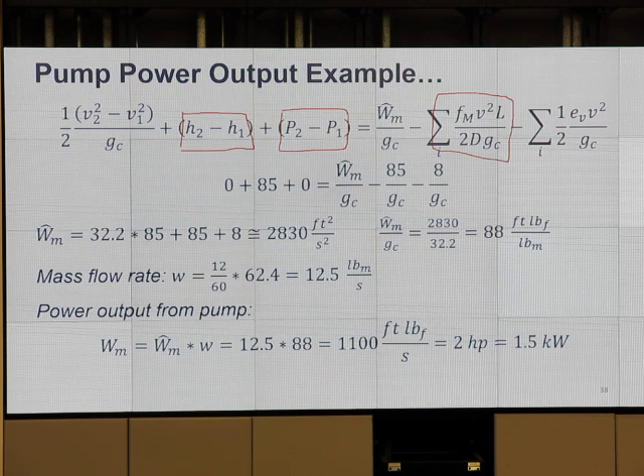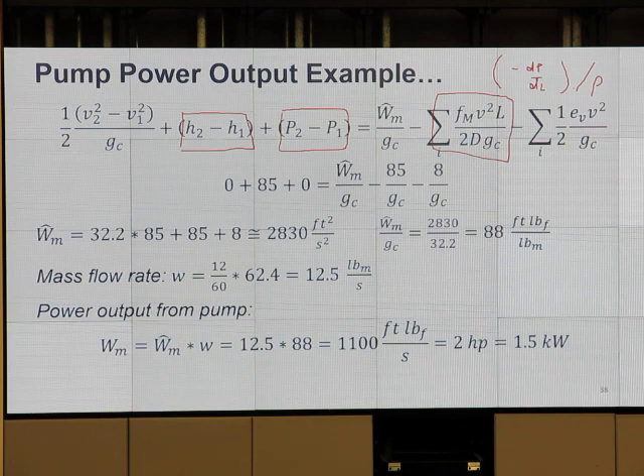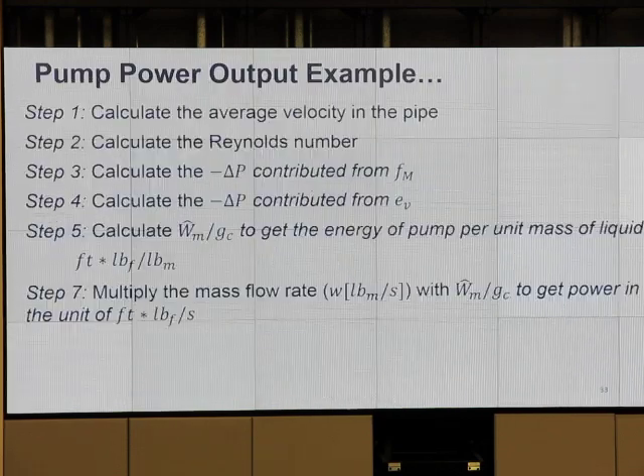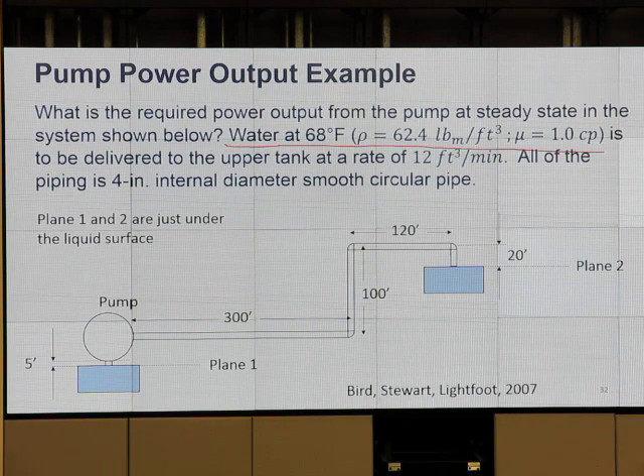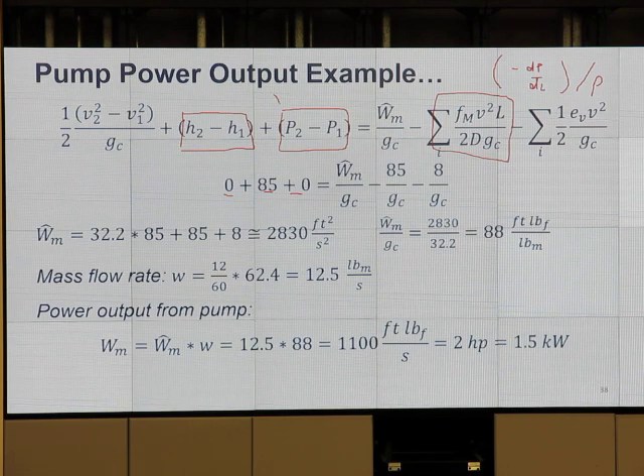You may notice F·V²·L over 2D·Gc — that is minus dP/dL, divided by density rho. So it's pressure drop per unit length, divided by density. In the example we have, you see the substitution: 0 plus 85 plus 0 — that is for the case of water. We say water and use the density of water to find the horsepower required for pumping water.